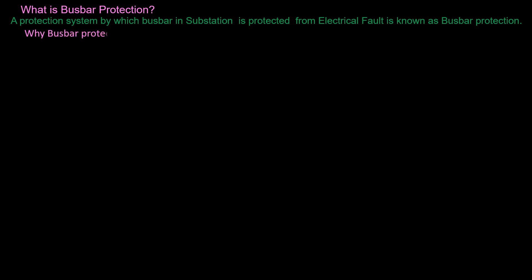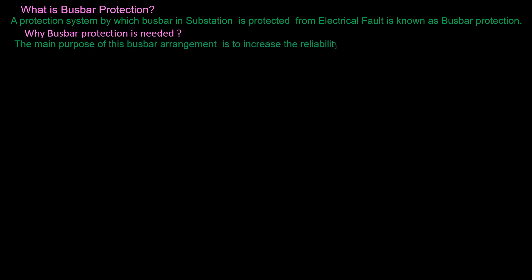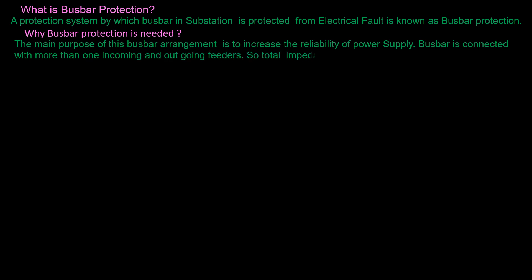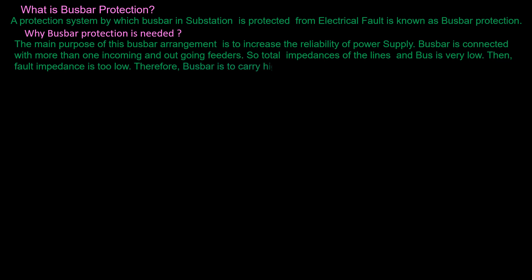Why is busbar protection needed? The main purpose of the busbar arrangement is to increase the reliability of power supply. Busbar is connected with more than one incoming and outgoing feeder. So the total impedance of the lines and the bus is very low, and therefore the fault impedance is too low. Hence the busbar has to carry high fault current during a fault, so protection of the busbar is needed.